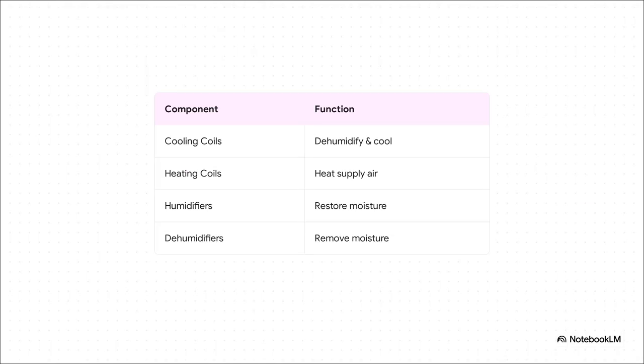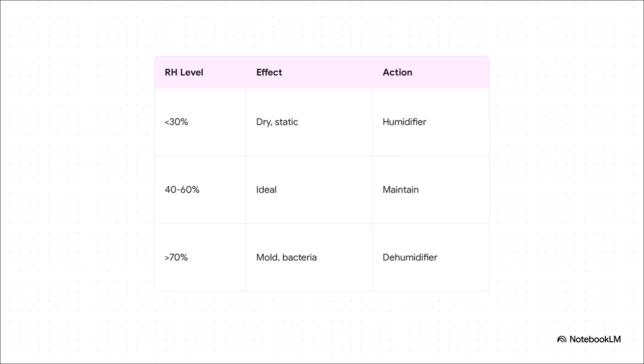Now, cooling and heating coils do exactly what you'd expect. Cooling coils use chilled water or DX refrigerant, while heating coils use indirect hot water or direct electric and gas heat. But handling excess moisture, that is where things get really fascinating. To dehumidify, the system actually overcools the air all the way down to its dew point. It literally wrings the water right out of it, forcing condensation. Then it uses a reheat coil to bring that air back up to the desired supply temperature, just without the excess moisture. It's a highly engineered, brute force process. Conversely, if the air is too dry, humidifiers step in to restore moisture using high-pressure spray, a steam pan, or a steam grid. You might be wondering, why does moisture control matter so much?